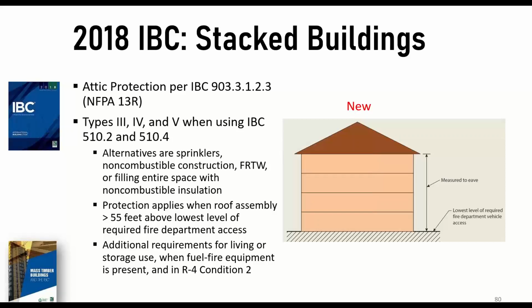So there was a code change passed for buildings protected with the limited sprinkler system, NFPA 13R, for the combustible types of construction 3, 4, and 5. As an alternative to sprinklering those spaces, you can construct them with non-combustible construction, fire-retardant-treated wood, or fill the entire space with non-combustible insulation. And the eave height of these buildings protected with NFPA 13R was reduced slightly to make things easier for fire department access. Instead of measuring from the average height of grade plane, we're now determining that measurement from the lowest level of required fire department vehicle access. In other words, how close can the firefighters get to the building? If they can get to the building, we want to measure those reduced, more stringent criteria from the level of fire department vehicle access.